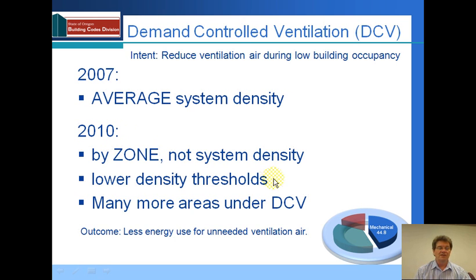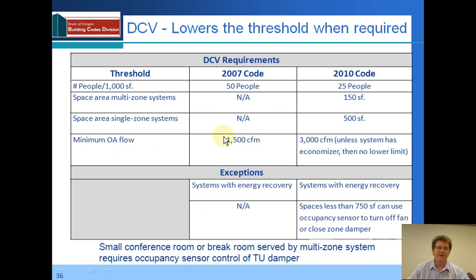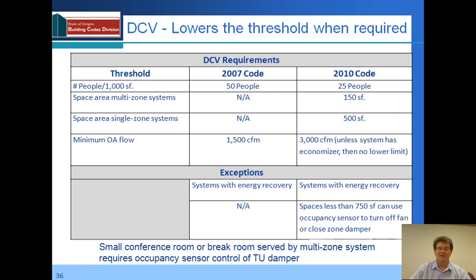As a result, there are lower density thresholds, and many more areas are going to have demand-controlled ventilation controls required. The threshold in people per 1,000 square feet under the old code was 50 people; now it's down to 25 people. So we're going to have areas that were across the borderline before now falling into a requirement. Because it's by zone, we do have some minimums: 150 square feet on a multi-zone system and 500 square feet on a single-zone system. Pretty much any unit that has an economizer will have this requirement, and if there's no economizer, it will have a requirement to have this type of control installed at 3,000 CFM of outside airflow.